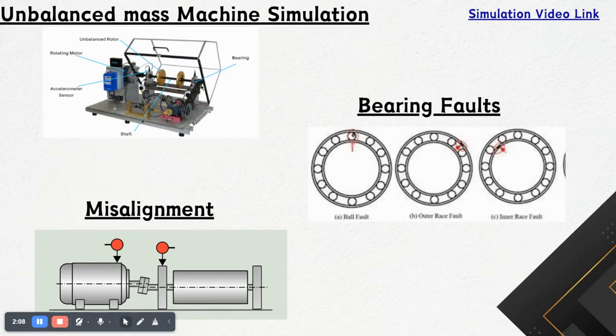That force will act outward, and due to that force, these rods get unstable and produce some kind of vibrations. Those vibrations are recorded by this sensor and exported to the Excel sheet. Those vibrations can damage your machine. If it is producing very high vibration, it can damage your machine. So this is the first type of fault which we have covered.